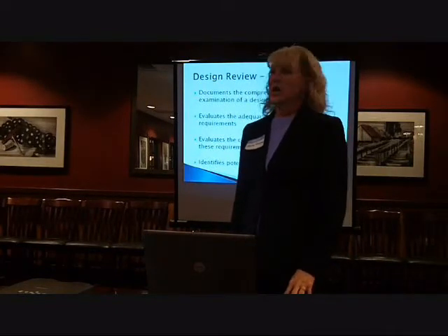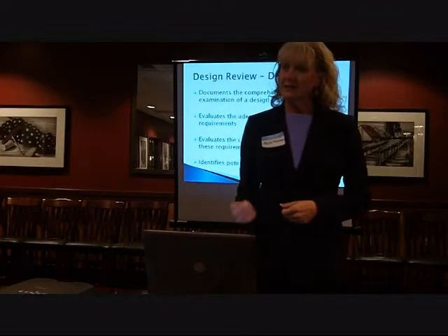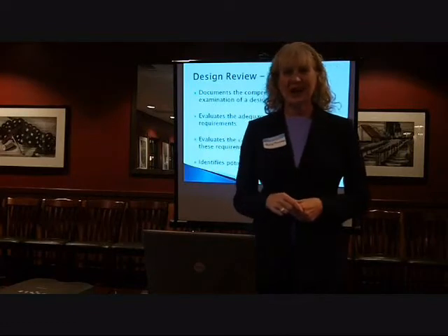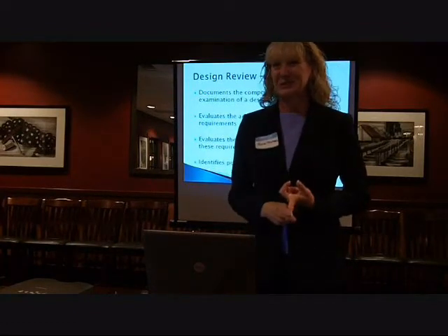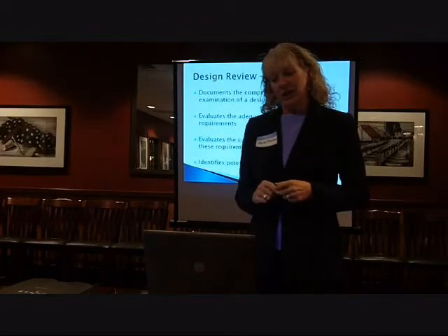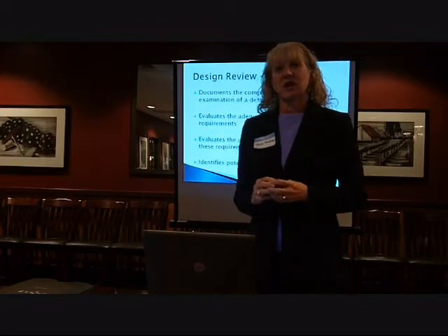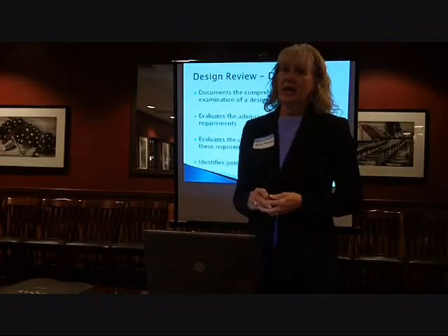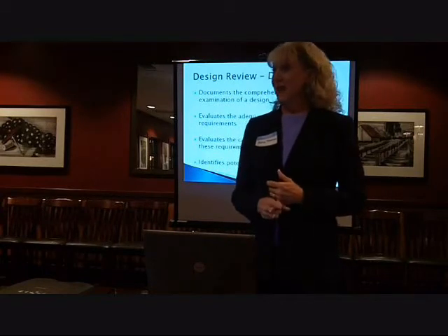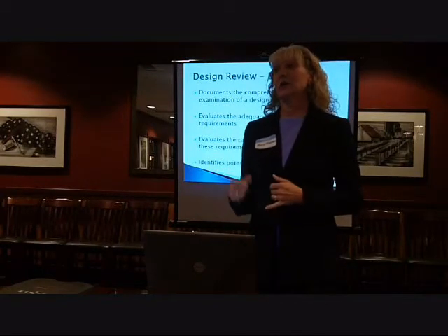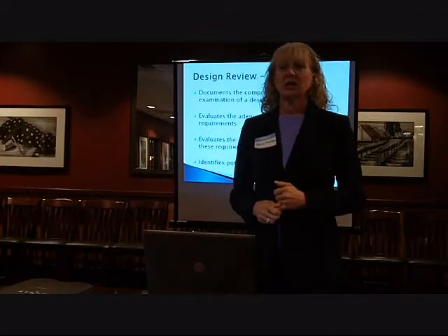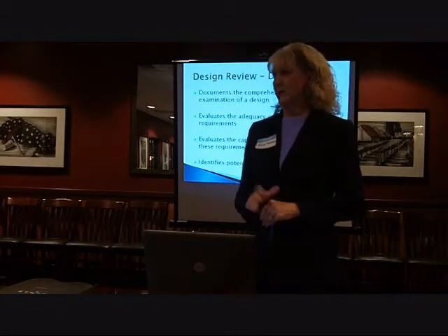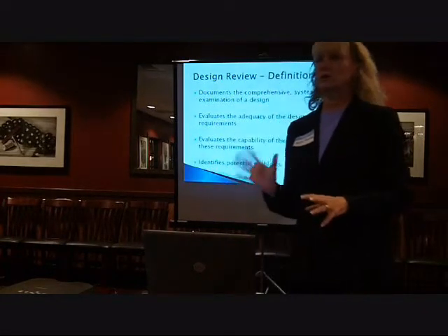The biggest thing in the design review, though, is that it is a mixture of people. The FDA actually spells out in the regulations that you need to have this wide variety of people in the room. You get a lot of perspectives in there, and you start to identify what could go wrong with this design. People are looking at it from a manufacturability standpoint, and we're going to look at this a little bit later, but this is where the flags get thrown up, and no, we can't do that. It'll be too heavy, or too big, or whatever.